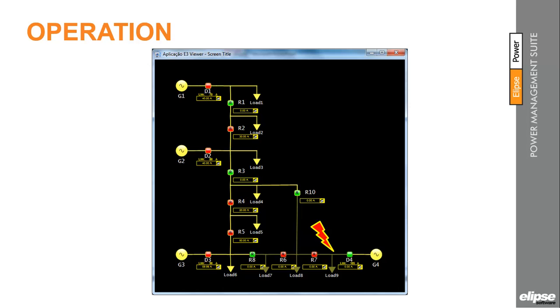So, simulating the fault, this is what happens. The system will perform the AC reclosing relay protection ANSI 79 so that the system is restored automatically, in the case of a transient fault. In general, the relay attempts 3 or 4 times to close with increasing timings at each step.